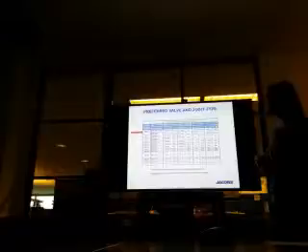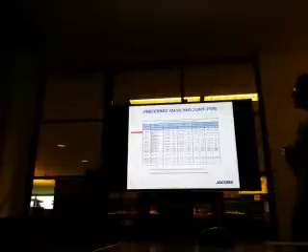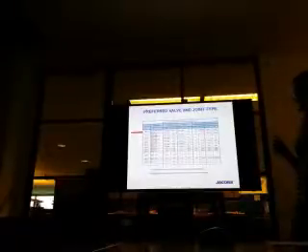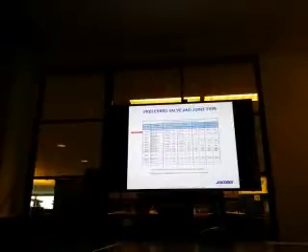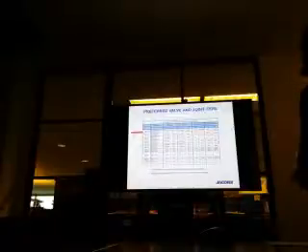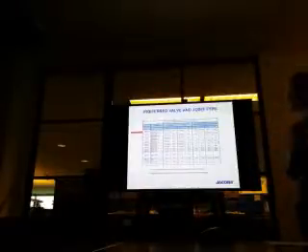It also summarizes each of the material specs, but because each of the material specs has more components in there than we may necessarily need, it's the preferences that we would use. So it's almost like a nice cliff notes to the spec. I don't know if they know what cliff notes are. But okay, so the first column is the material, and sure enough, if you go look, the first highlighted item tells you that it's carbon steel pipe. Carbon steel pipe's a good material. We can use it for cold services, chilled water in this case. You can use it for hot services.